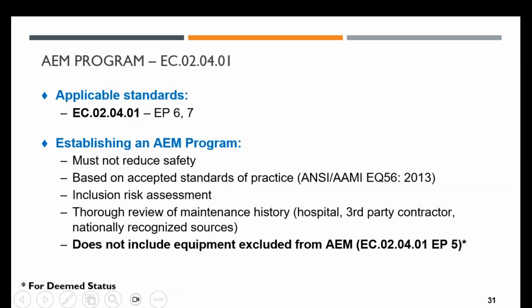Okay, a bit more about AEMs. So you've heard me reference AEM, or an alternative equipment maintenance program. And really what this means is that it's a program or maintenance strategy that deviates from the manufacturer's recommendations for devices in that program. That could be in the frequency of the PM schedule. That could also be in the actual procedures that occur during the maintenance. And the Joint Commission standards that apply specifically to AEMs are listed on the slide.